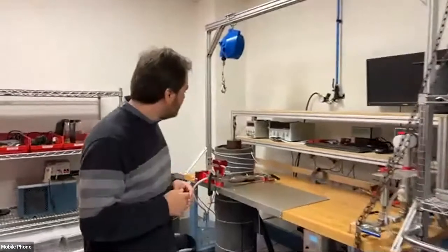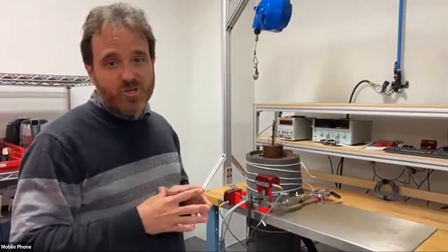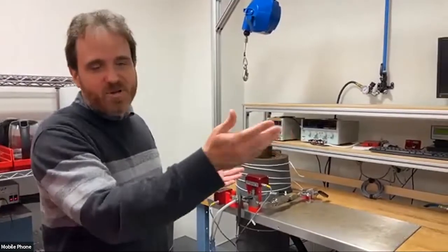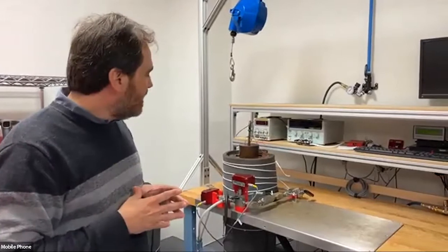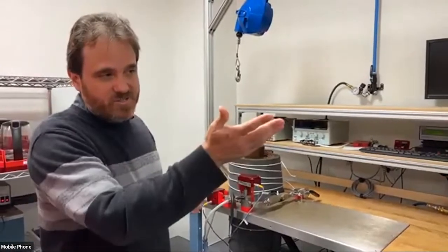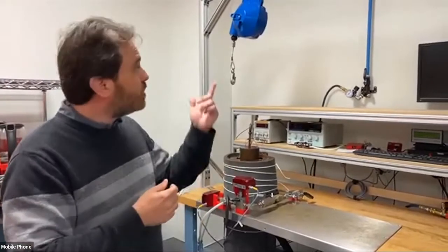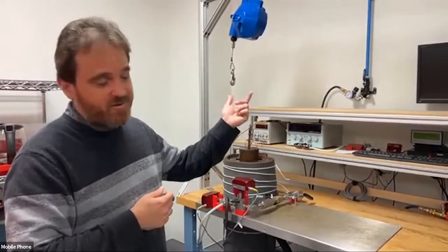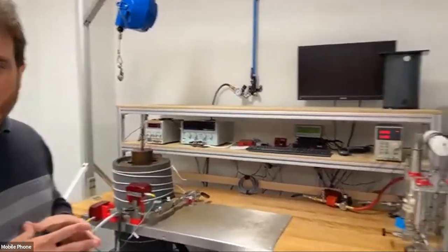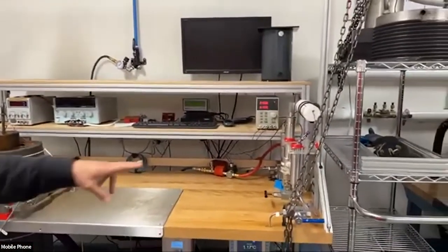And if you can just follow me over this direction. This pressure vessel is where we test all our high pressure instruments. High pressure meaning above 2,000 all the way up to 10,000 dbar. This system works a little differently than the previous system that I showed you. This one actually works with shop compressed air, and we have an in-house developed system working with a compressor.